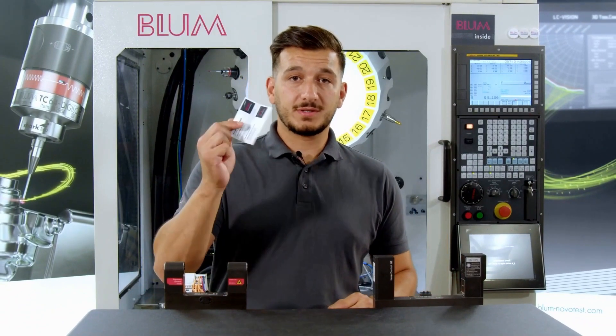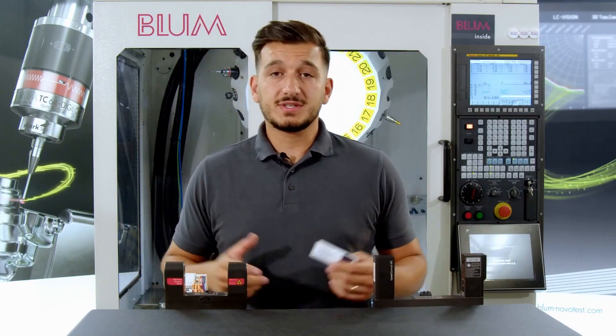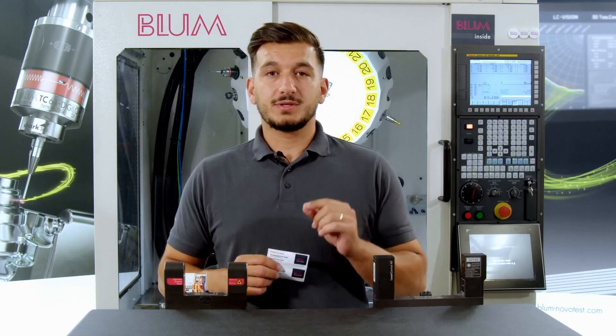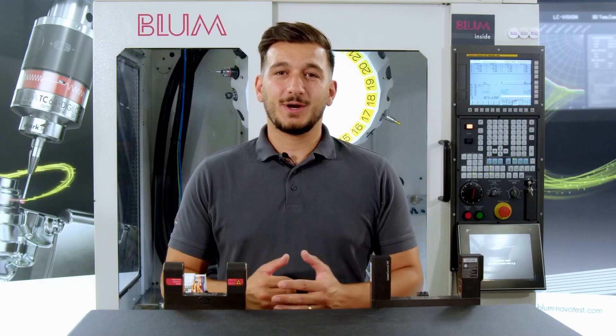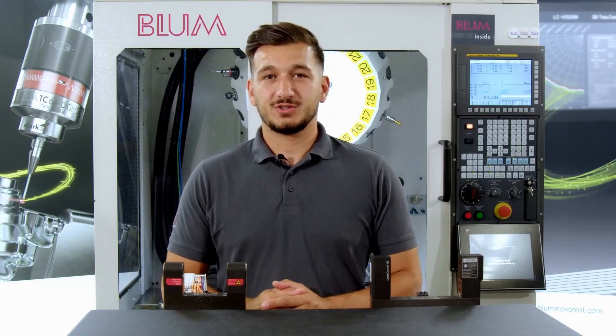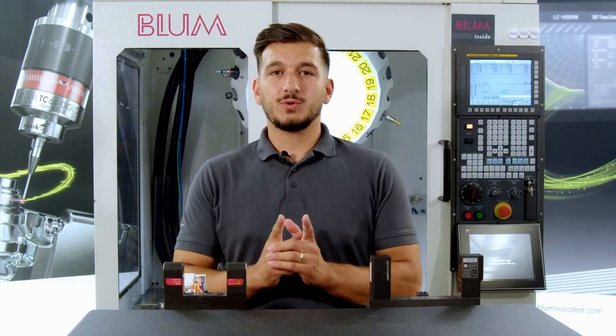What should we do next? You can either grab a glasses cleaning cloth or a commercially available microfiber cloth for cleaning. This is extremely important: please do not use any cleaning agents or substances of any kind. After taking apart the dirt covers and cleaning the laser, we proceed to test the function once more. It is extremely important — do not use coolant.